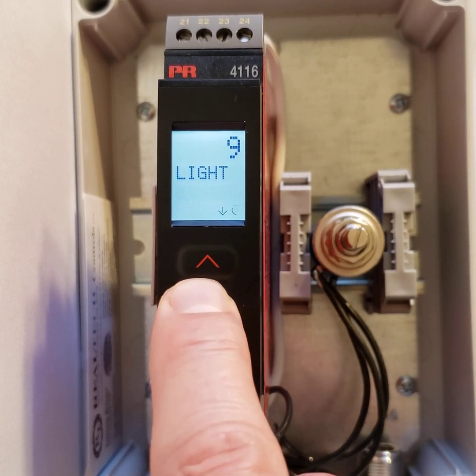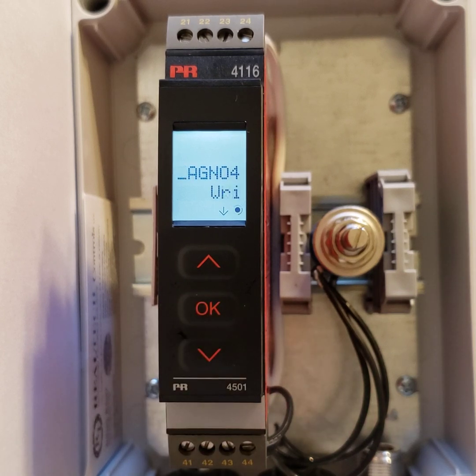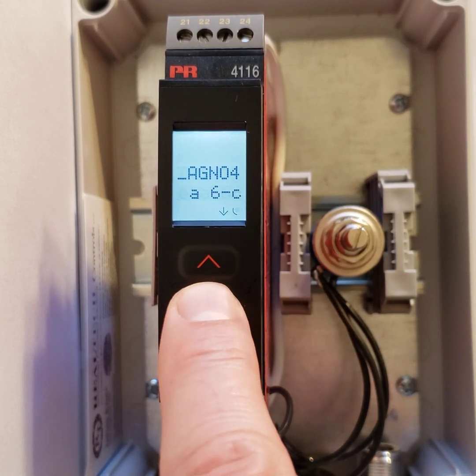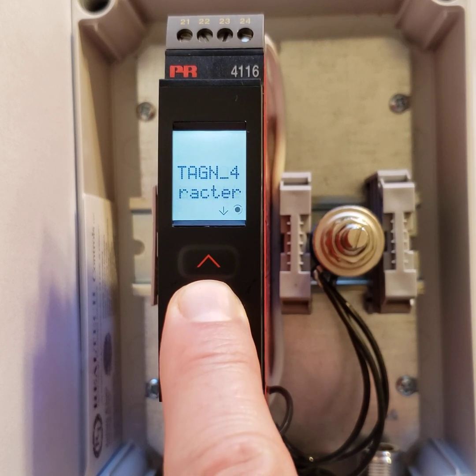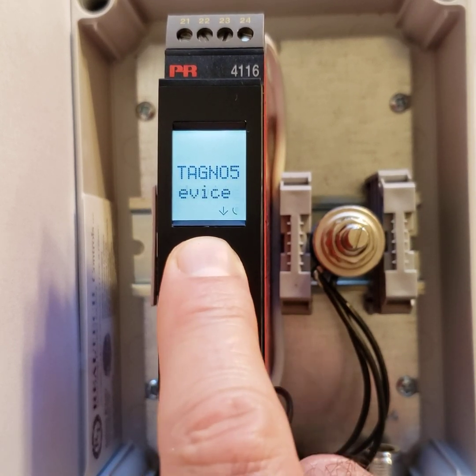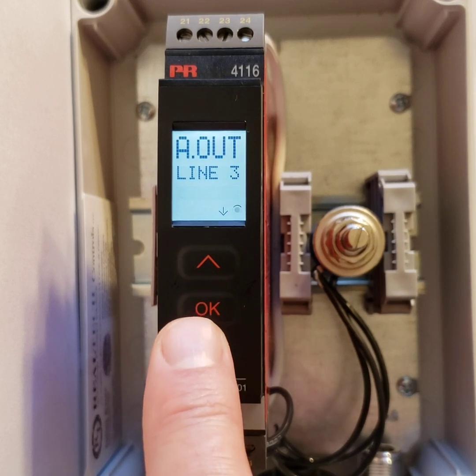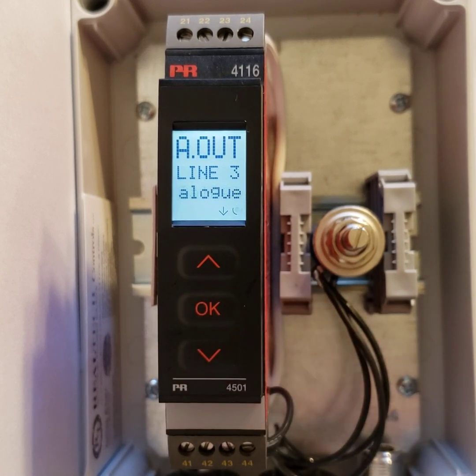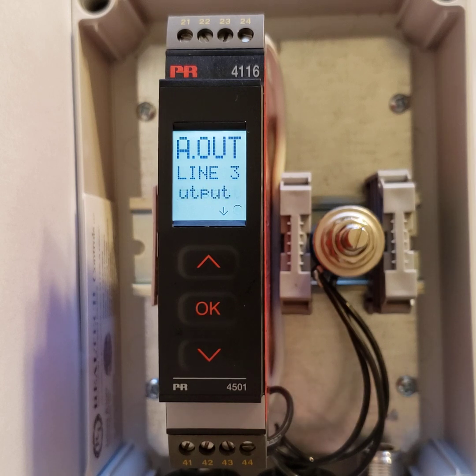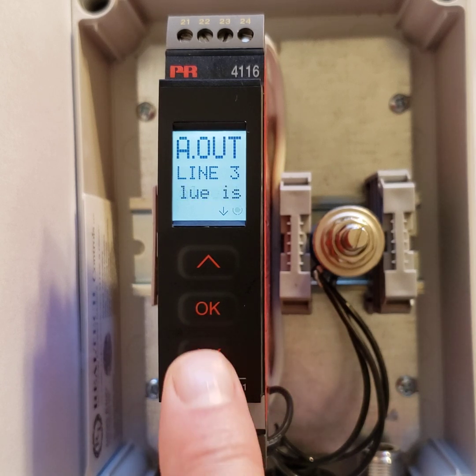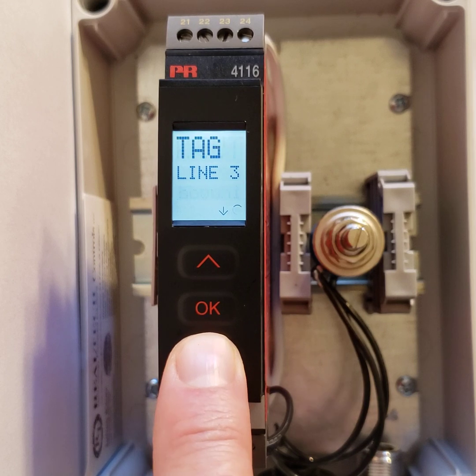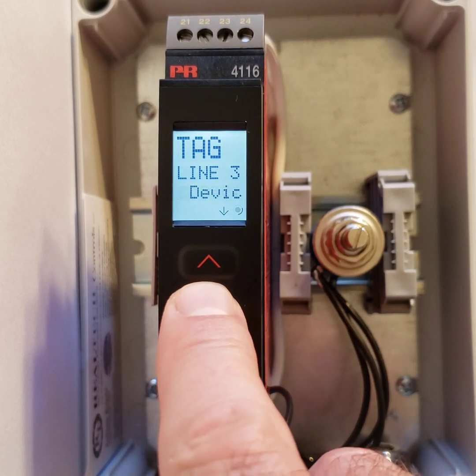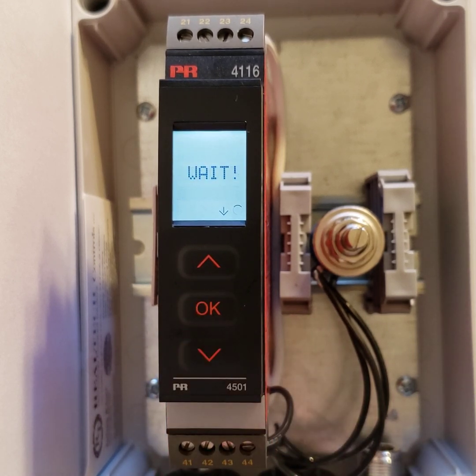Mine is the brightest. You can also choose a tag or label number for this device. So at the moment, it's set at tag 04. You can change that to say tag 05. Now it gives you an option. What do you want to show on line 3 of the device where the instructions are scrolling across at the bottom at the moment? You can choose the analog value, which we had, or we can choose the tag. So we're going to choose the tag, and you'll see now that the tag is shown at the bottom, so you can have the label of the device if the milliamp output is not important.